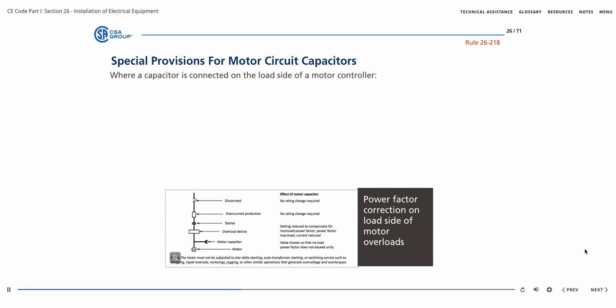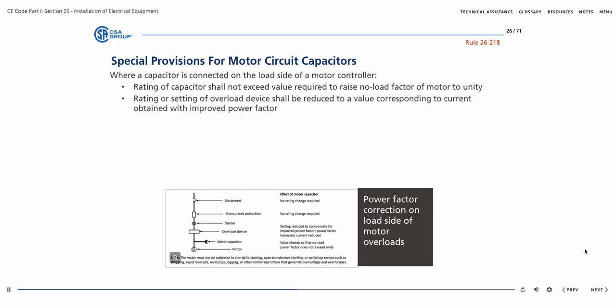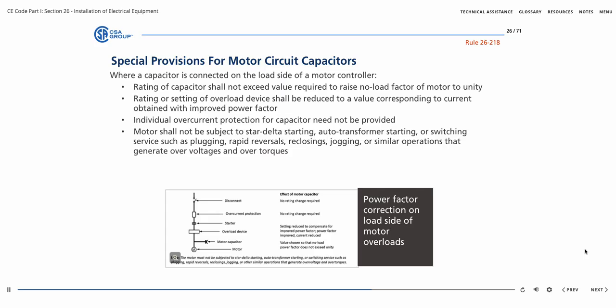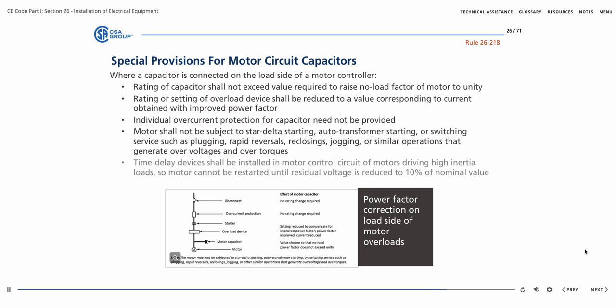Where a capacitor is connected on the load side of a motor controller, the rating of the capacitor shall not exceed the value required to raise the no-load power factor of the motor to unity. The rating or setting of the overload device shall be reduced to a value corresponding to the current obtained with the improved power factor. Individual overcurrent protection for the capacitor need not be provided. The motor shall not be subject to star-delta starting, auto-transformer starting, or switching service such as plugging, rapid reversals, reclosings, jogging, or other similar operations that generate overvoltages and overtorques, and time delay devices shall be installed in the motor control circuit of motors driving high inertial loads, so that the motor cannot be restarted until the residual voltage is reduced to 10% of the nominal value.